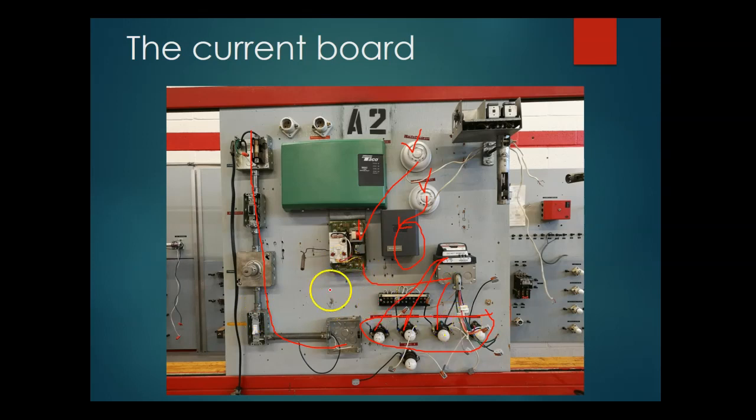We have a red wire over here, and the hot line here will connect to the line voltage. Neutral will connect to the neutral as well, and C1 and C2, we'll use those two as circulators, circulator 1 and circulator 2. So we'll put a light bulb, and one of them will go to C1 over here, and C2 will come to here, and so on.